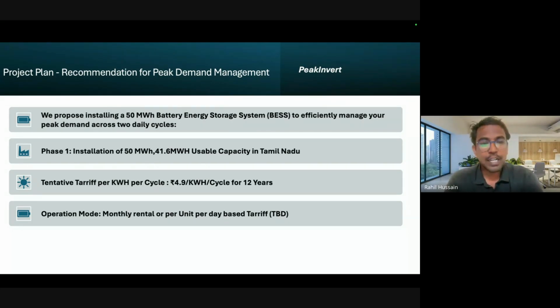For one of our clients, we planned a 50 megawatt hour storage system, located in Tamil Nadu itself. We size the BESS such that 80% of it will be utilized and 20% will be theoretically oversized, as a design to cope with losses. There's a concept called depth of discharge in batteries, and at max you can do 80% depth of discharge for longer battery life cycles.